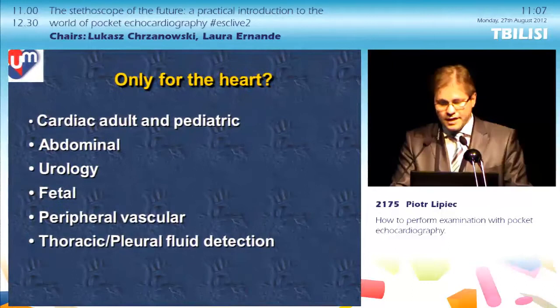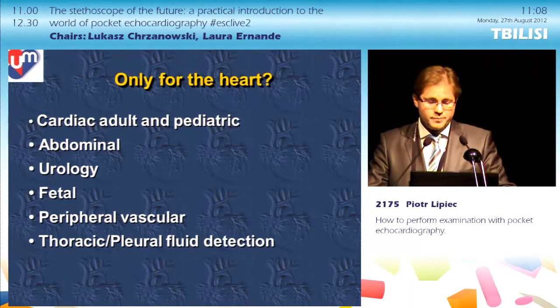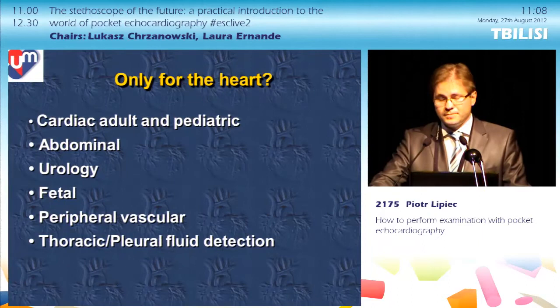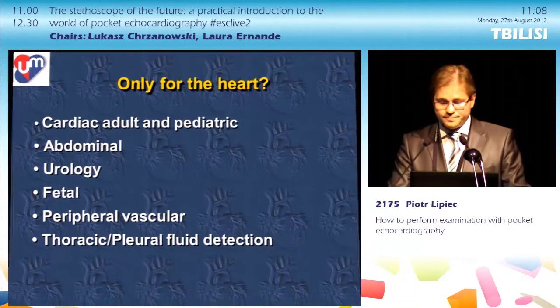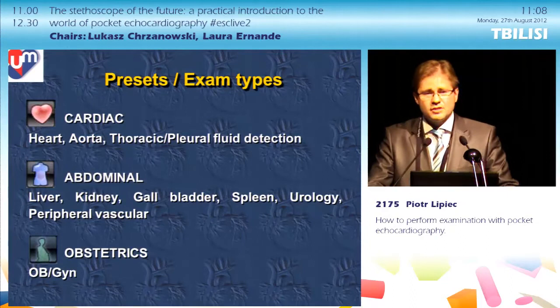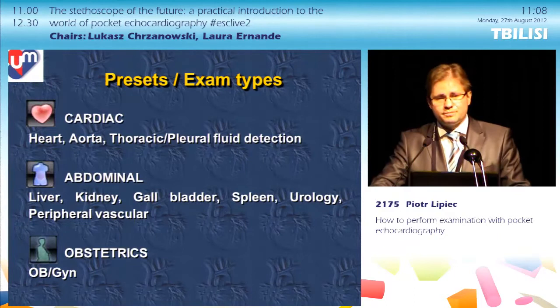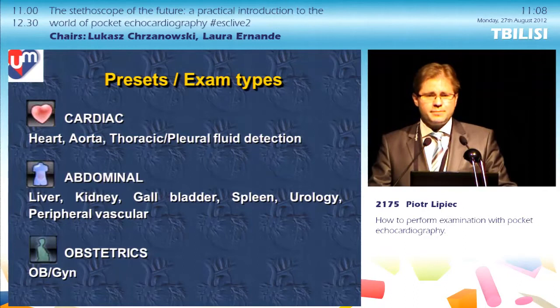Although the session title is Pocket Echocardiography, the device is not used mainly for the heart. You can use it for cardiac examination, but also for abdominal examination, urology, fetal examination, peripheral vascular examination, and detection of pleural fluid. Looking at the available presets, there is a cardiac preset, an abdominal preset suggested by the producer for peripheral vascular examination — where the cardiac preset can also give good results — and an obstetric preset.